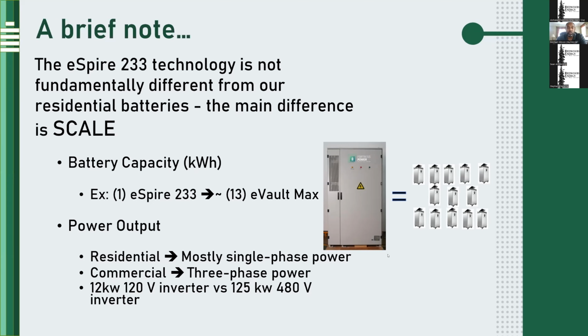What is the difference between the eSpire residential versus commercial? The biggest thing is the inverter and the power capacity. With an eSpire, you're essentially going to a 480 volt, 3-phase, 3-wire system. When you look at true commercial voltages, generally you're looking at more storage capacity and 480 volt voltage, which is what you'll find in most industrial occupied buildings around the country.